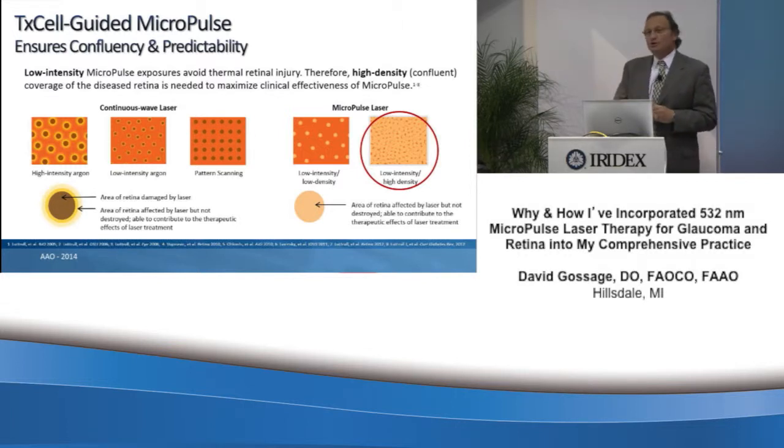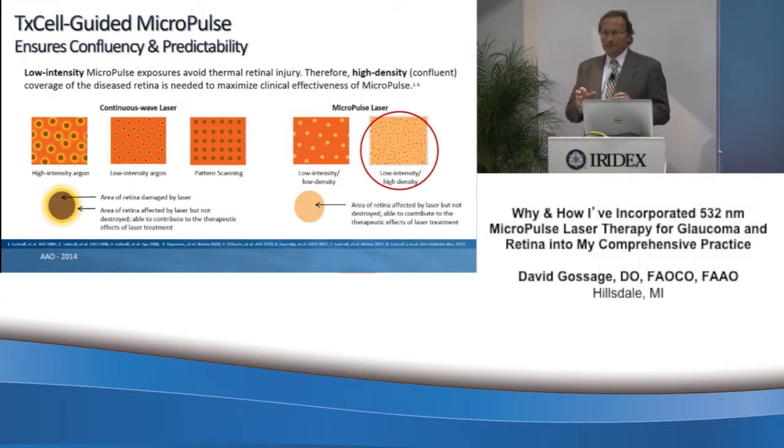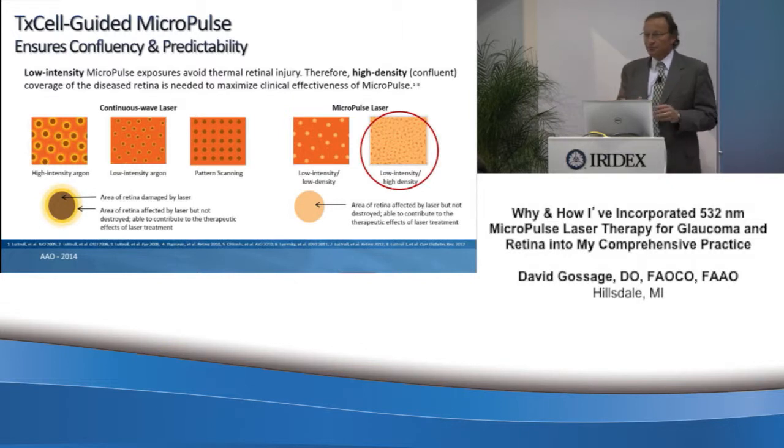The big thing with MicroPulse, and what I would stress to you, is that when you're dealing with retina, you don't want to use anything higher than a 5% duty cycle.